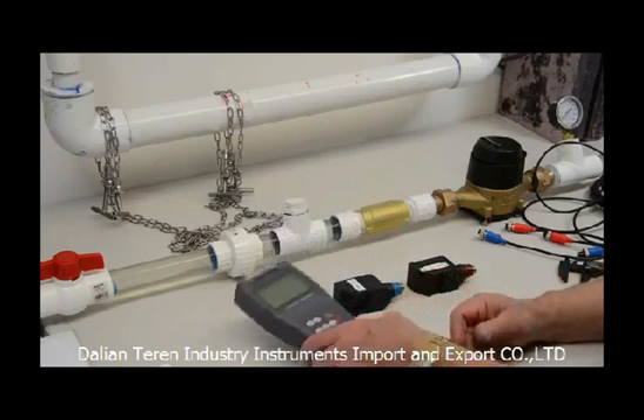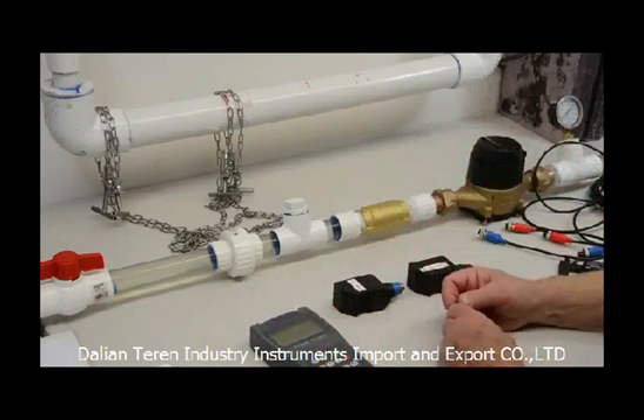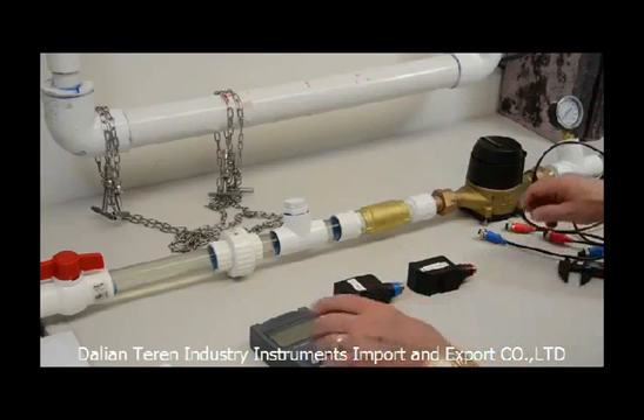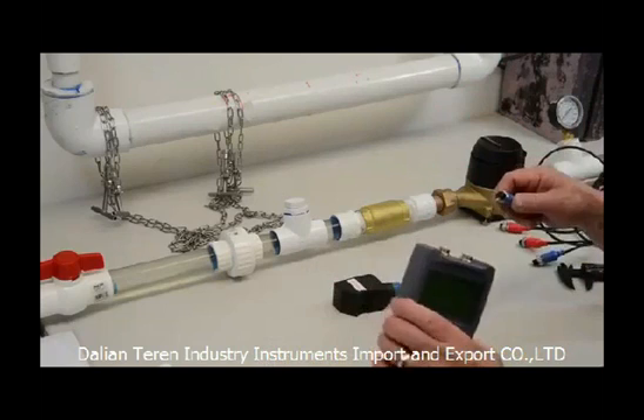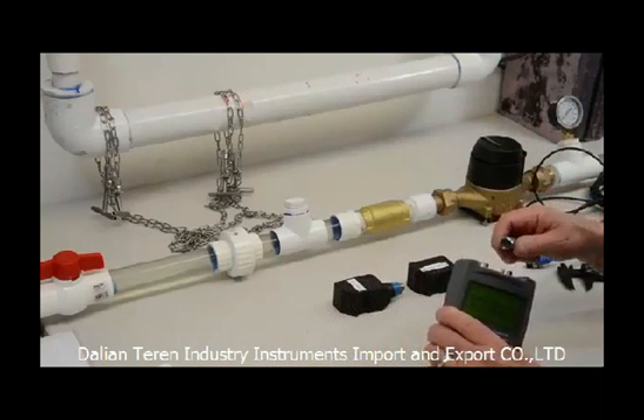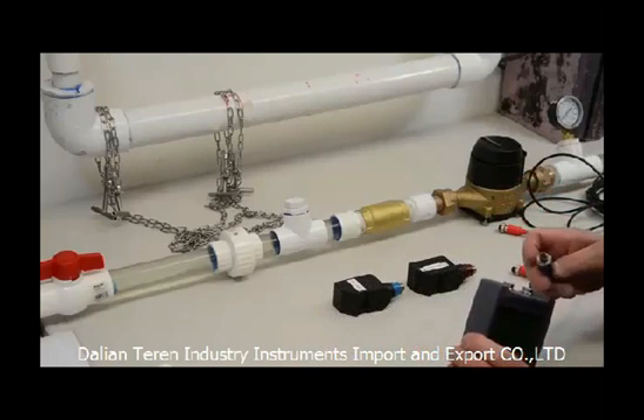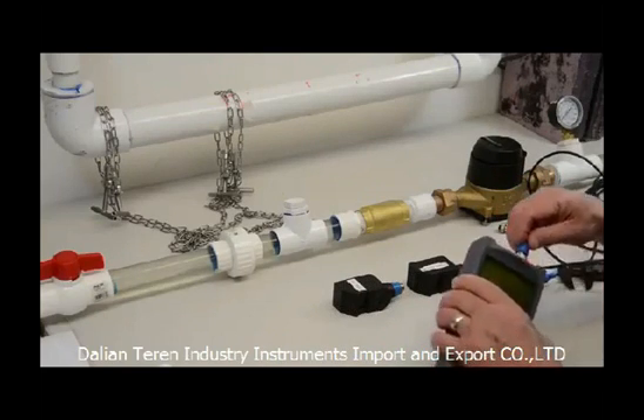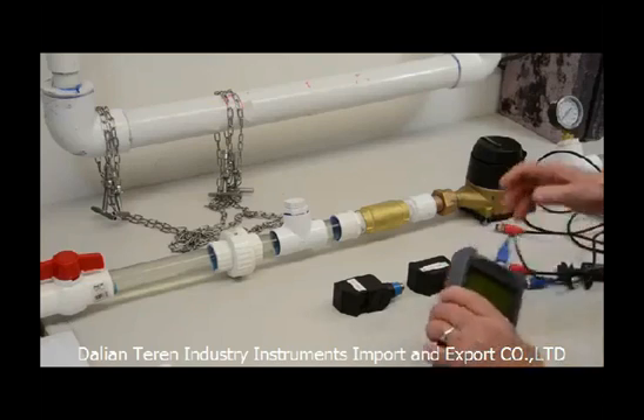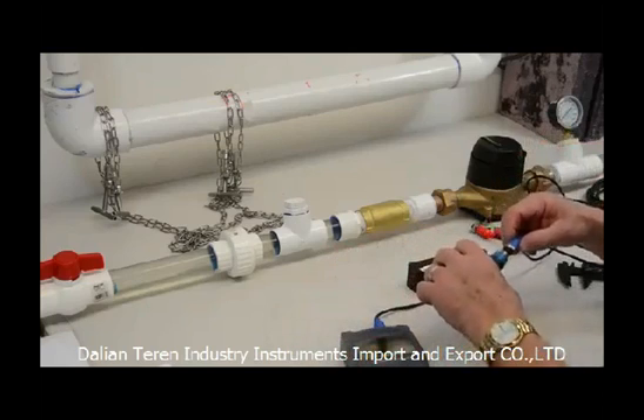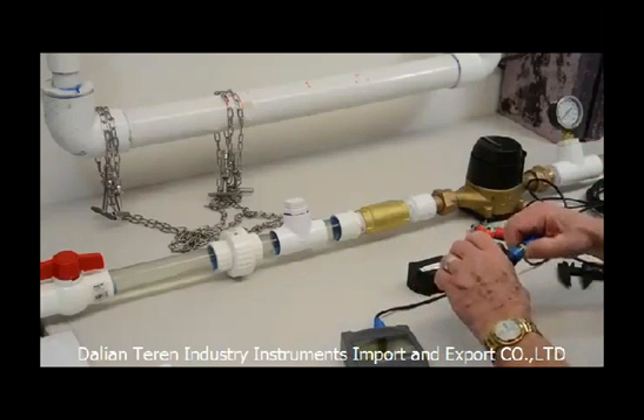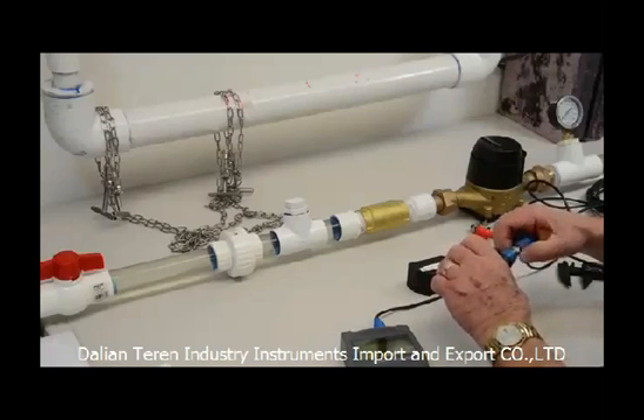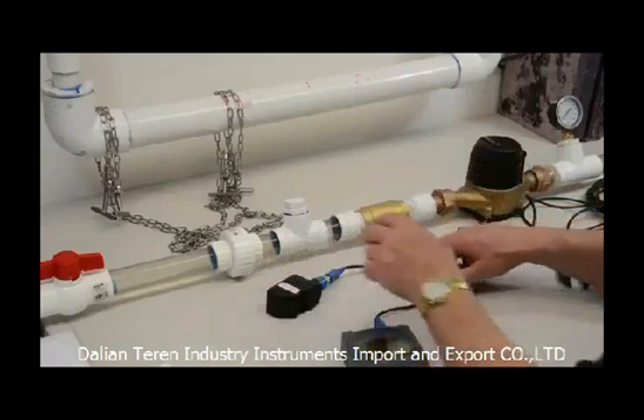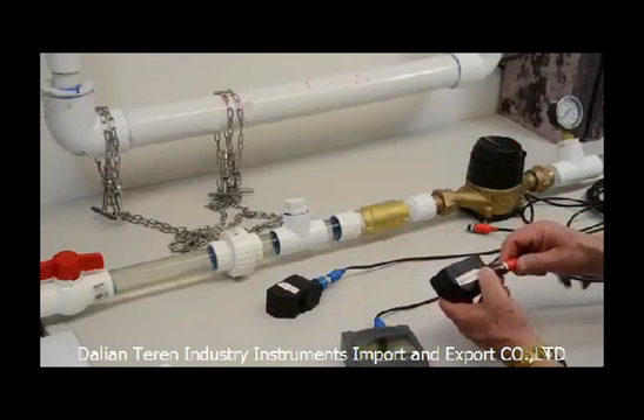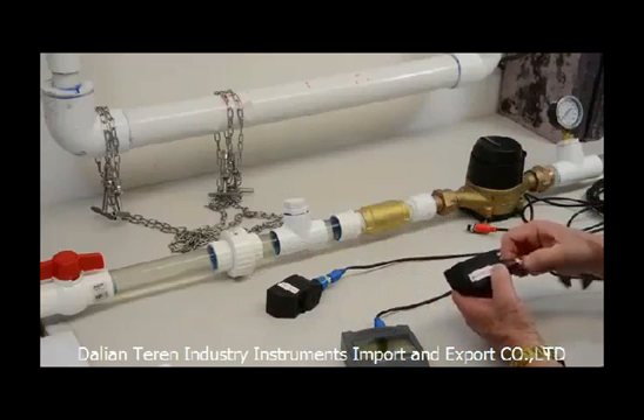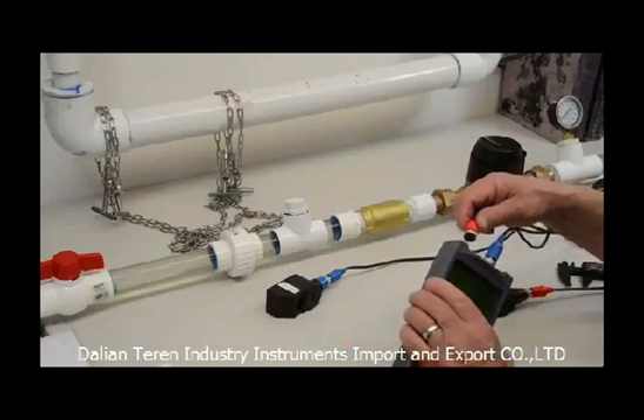So now what I'm going to do, I'm going to mount the transducers, and the first thing I'm going to do is attach my cables to the flow meter, and I'm going to attach the blue cable to the blue section, which is the downstream. So I just insert that and hook the downstream transducer to that. There's no particular way you do this, just be sure that you get the proper transducer to the proper colored cable so that you don't have any confusion.